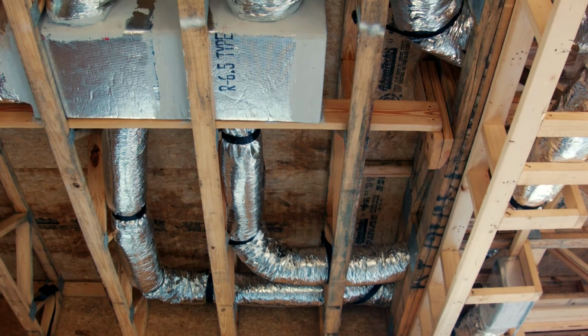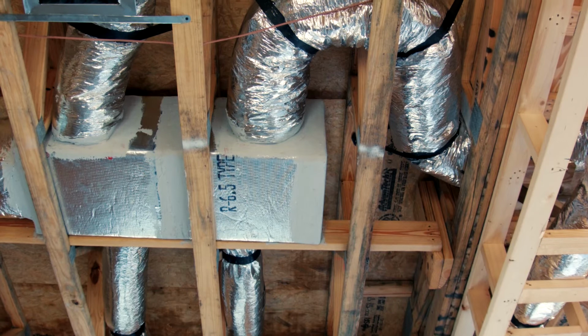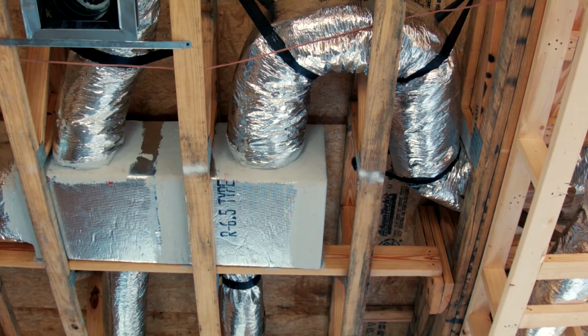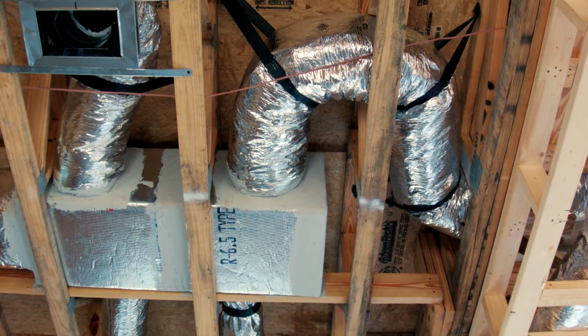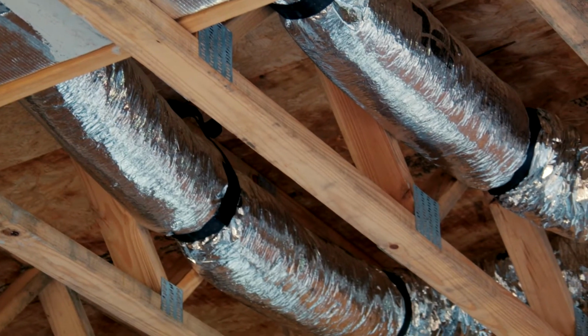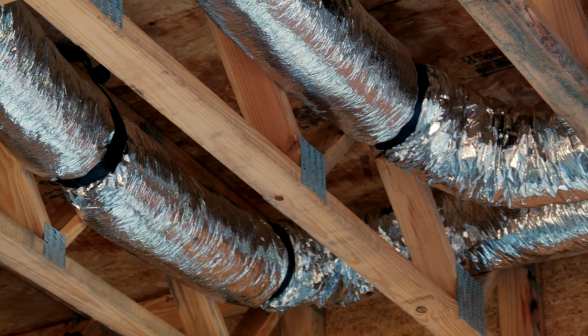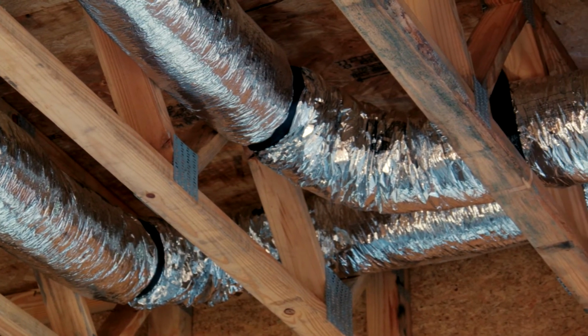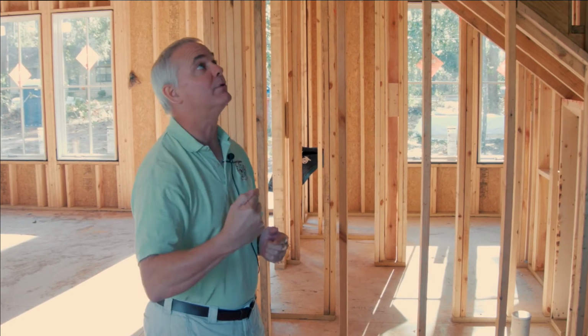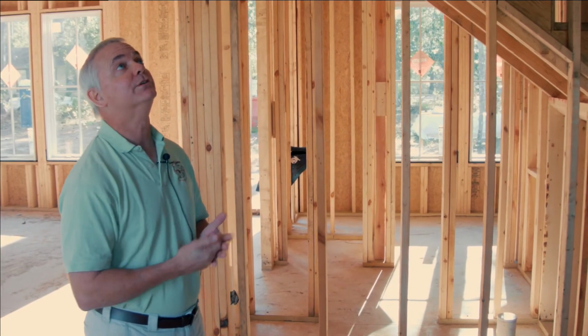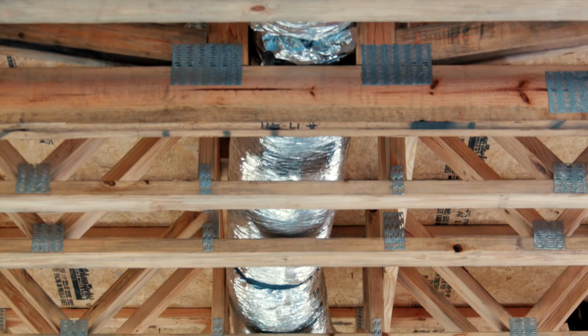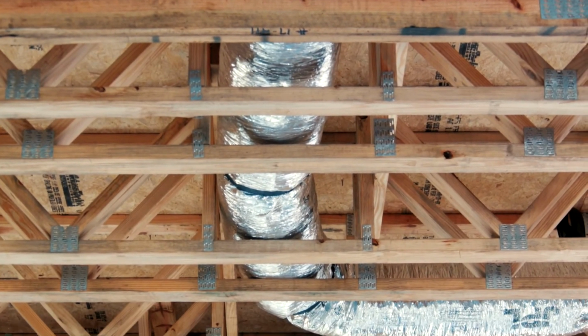Up here with this supply ductwork, one thing we often see in an effort to seal these tight, installers will use a strap and zip it up really tight. And what that'll do is it'll pinch the insulation on the ductwork, and then that ductwork won't insulate. It'll get cold enough to condense, and then you'll get staining and that kind of thing. So our team is very careful to not compress that, but they maintain a good air seal with both tape and mastic. We have mastic that you can see, and then mastic on the inner layer that you can't see. It's what we call our 3 seals program. We have 3 separate, redundant efforts made at every joint to make sure that's airtight, that this stuff will pass a duct blaster test and put the air where it needs to be, not where it doesn't need to be.